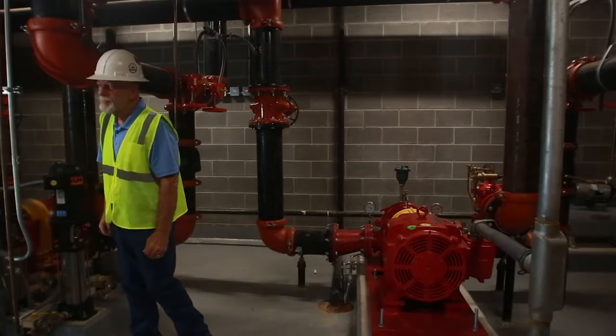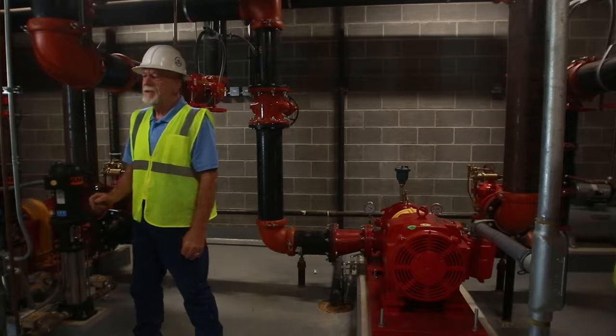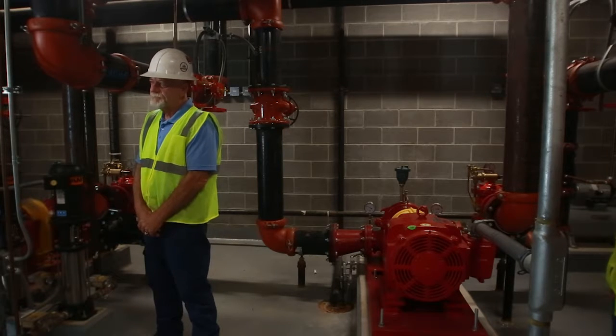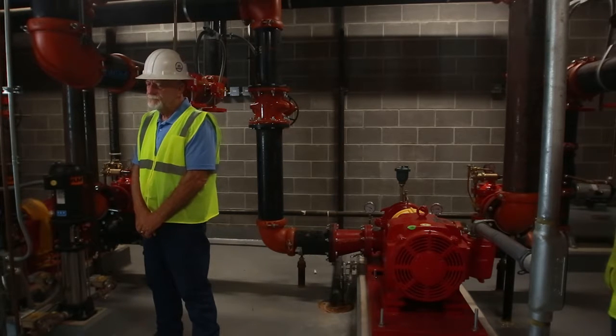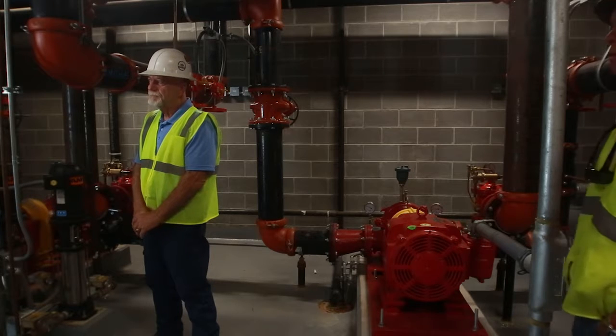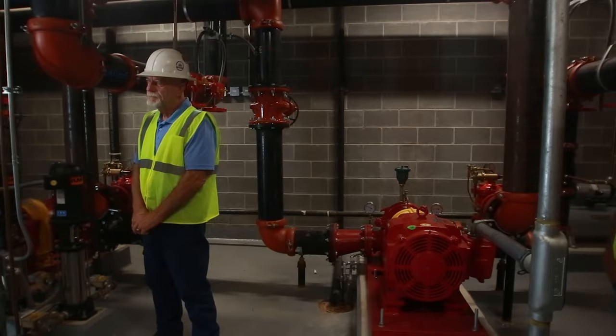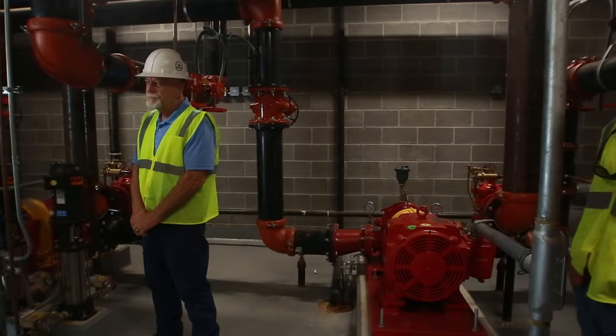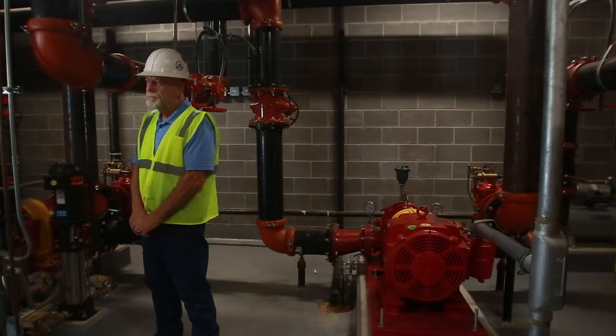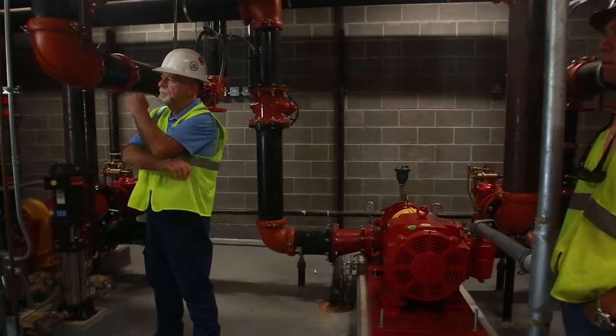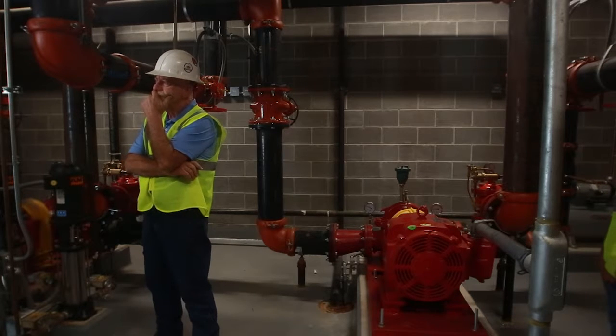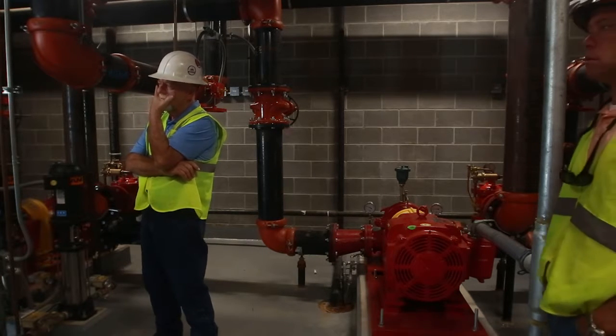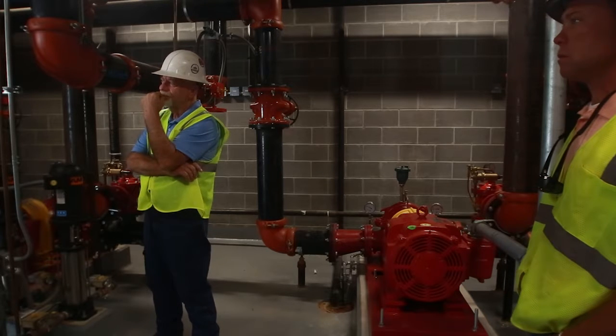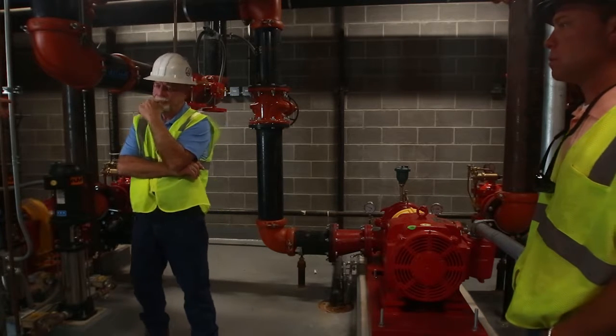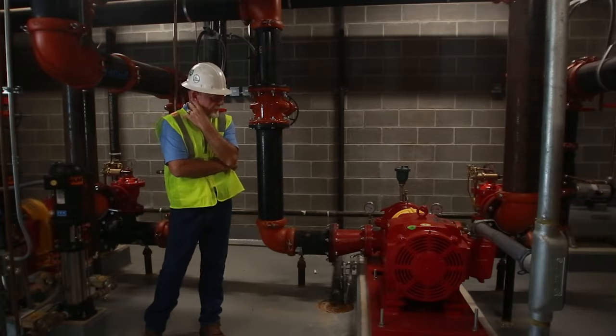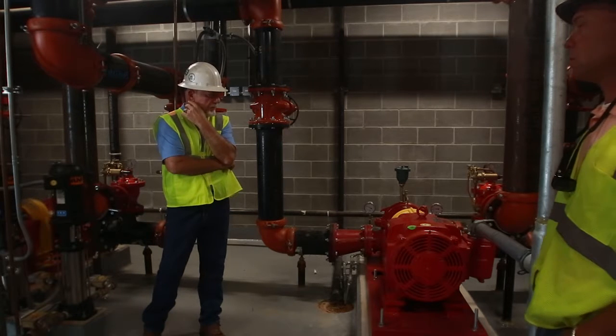How should we test these things if we test them? Because I know, like up at building one, up at parking deck one, if that pressure is not 155 or higher before we start our test, the pumps turn on wide open. Boom, I mean, hit hard, come on wide open. Because with these variable speeds, testing is a little different. And when we do test it, should we test it to where it triggers the relief valve and let the water flow, or should we just test it and let it churn?